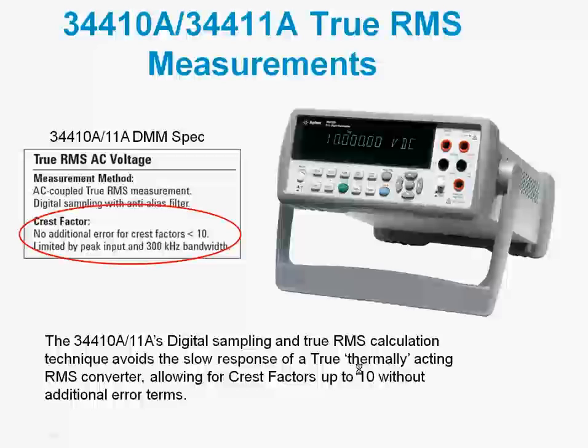The 34410A and 34411A DMMs actually use a slightly different technique. Instead of using thermal conversion, they actually do digital sampling — they digitize the incoming waveform and then perform a true RMS calculation.